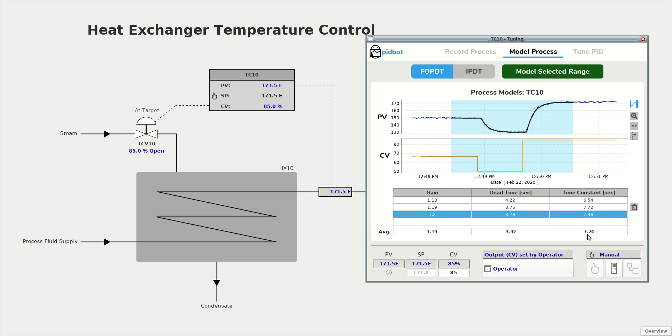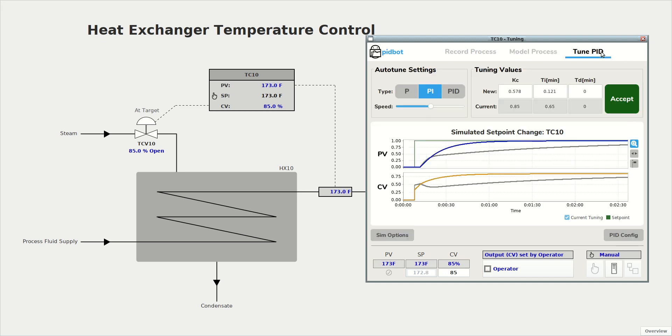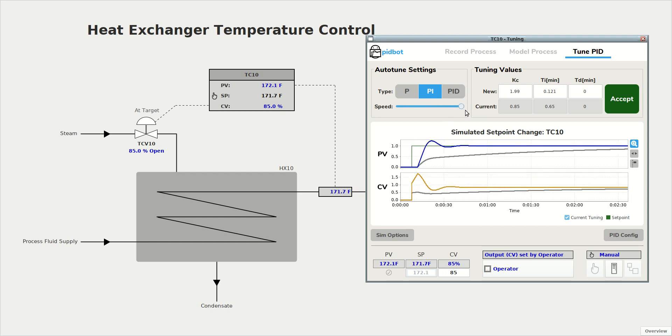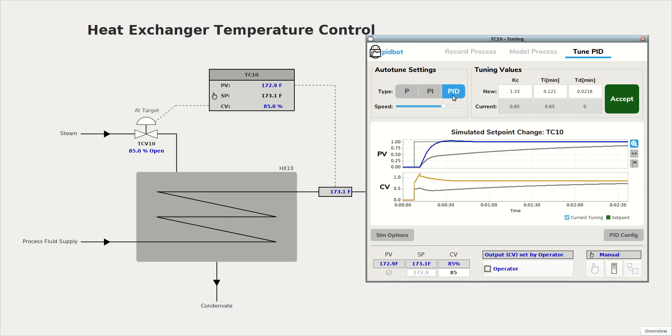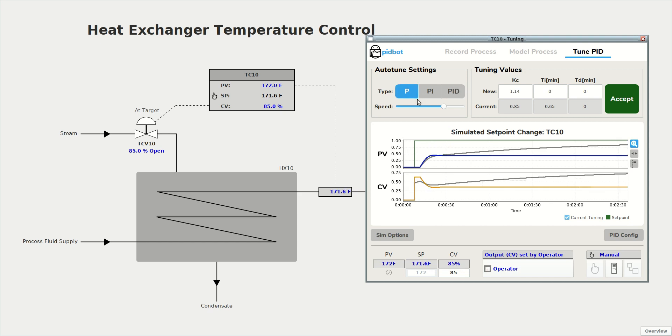So that looks pretty good. We can now go to the third tab where we tune our PID controller. Here's a simulated set point step response with our existing tuning values shown in gray here. And the temperature response looks a bit sluggish. The blue line represents the response with the new tuning values that are suggested by PIDBOT. And we can play around with those values. We can make that go faster if we like or slower. Or maybe we want to do proportional, integral and derivative. Or maybe proportional only.